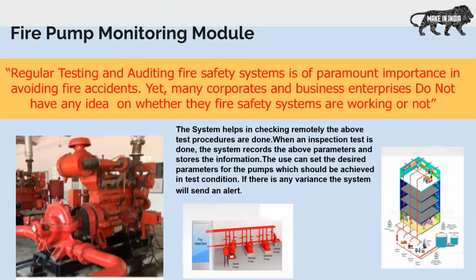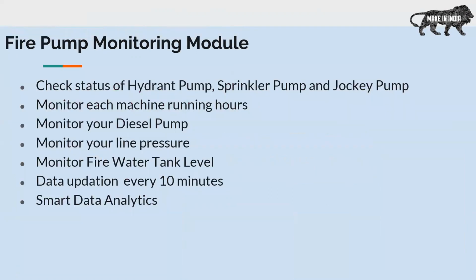So here we have a system where we can check the status of the hydrant pump, sprinkler pump and jockey pump. We can monitor each machine's runtime, then monitor the diesel pump. In the diesel pump, we monitor the fuel level, that is the current fuel level, the amount of fuel poured, the fuel consumed during runtime, and the battery voltage. Then we monitor the line pressure and the fire water tank level.